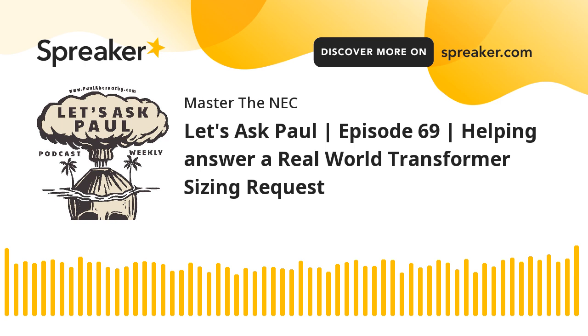I'm just saying it might be an option under 230.2. You might be able to bring an additional service to this building, and maybe under 230.2(D), which covers different characteristics. Okay, so this is different voltages. So you might have a 480, 277 there, but you might be able to bring a 120, 208 there or something like that, and you'd be okay to do that. Maybe that's more cost effective for you. But if not, you're going to go with the transformer route.